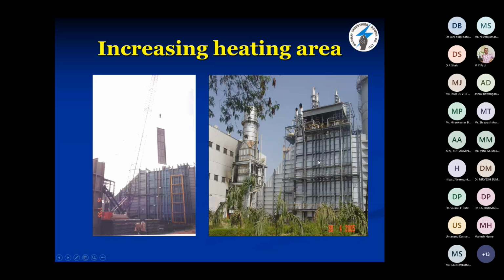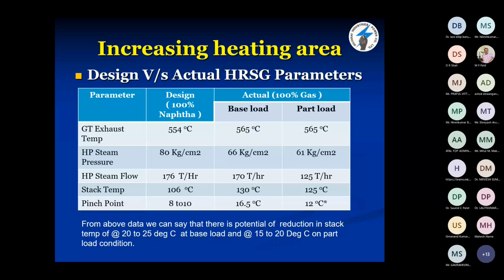Okay, then we have studied all the parameters of HRSG, and we have come to the conclusion that by increasing the heating surface area of the HRSG, we can increase the load of steam turbine and reduce the stack temperature. I will show you the parameters of our boiler. So, this was the design parameters versus this is the actual HRSG parameter.